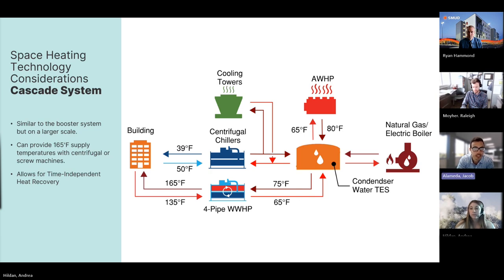But in this configuration, you have a condenser water storage tank that acts as your water source, and hopefully you can charge that tank most of the year using your centrifugal chillers. So instead of rejecting your heat from your chillers to cooling towers, you can capture and store that heat in the condenser water tank. And then you use water source heat pumps to extract heat out of the condenser water tank, and you can generate 165-degree water with those pieces of equipment.